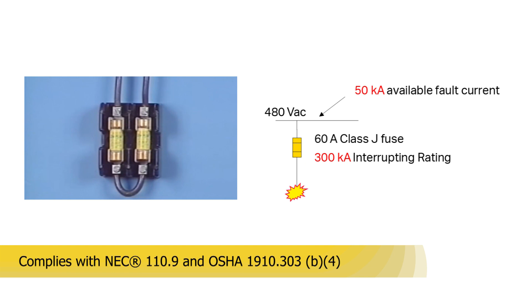As depicted in these tests, it is absolutely necessary to determine the available fault current at the line side terminals of each overcurrent protective device. The advantage of high 200 kA or 300 kA fuse interrupting ratings is that they can be applied to eliminate the need for fault current calculations, as these high interrupting ratings will exceed the available fault currents for virtually all power distribution systems.